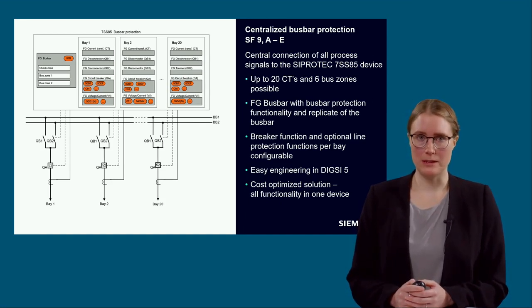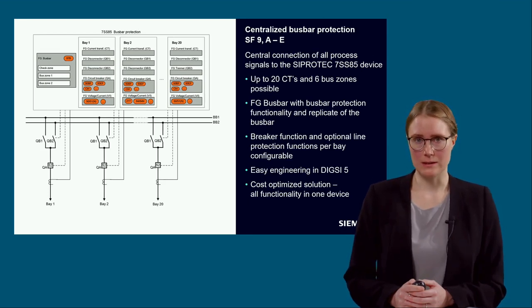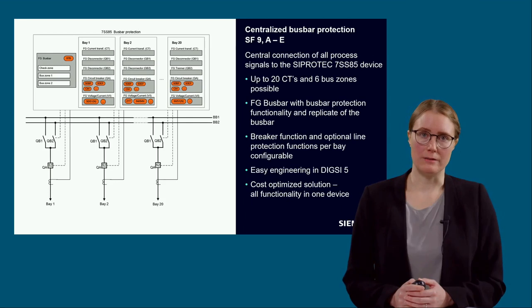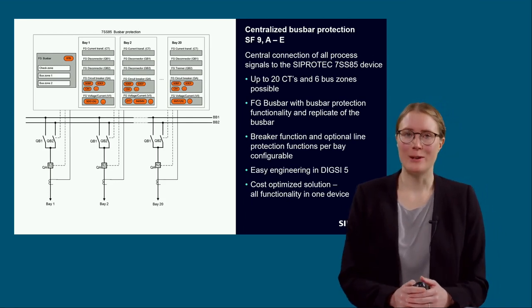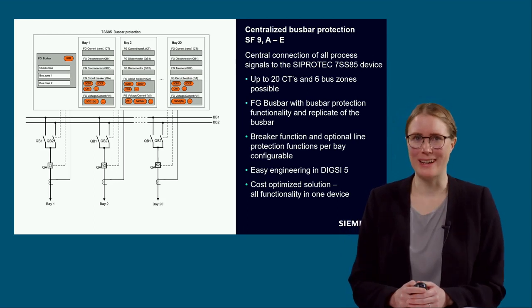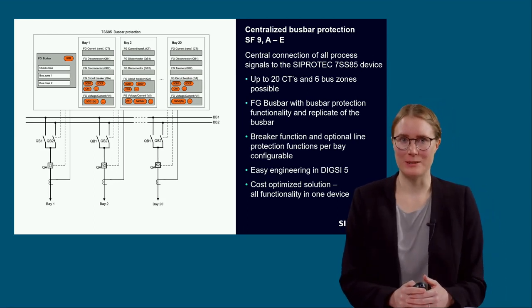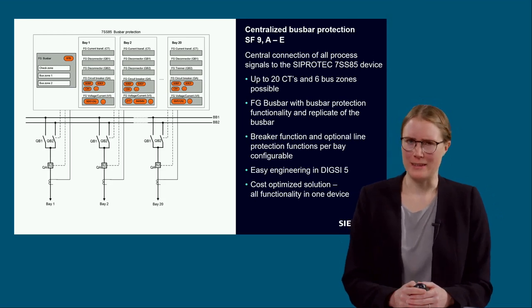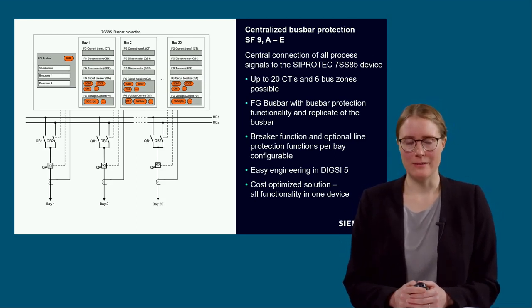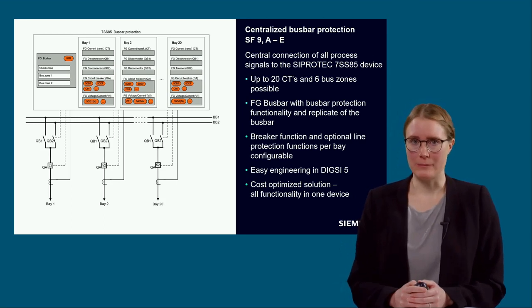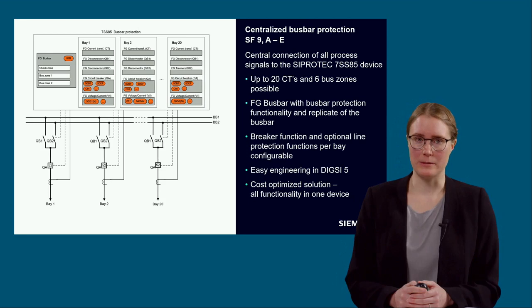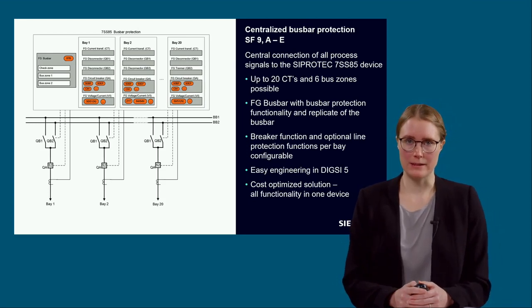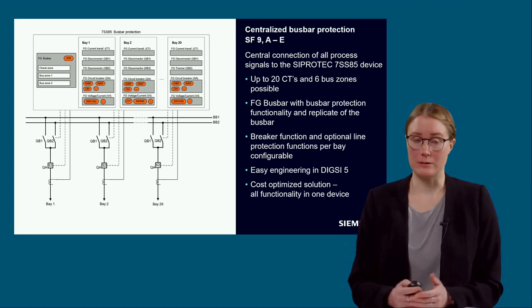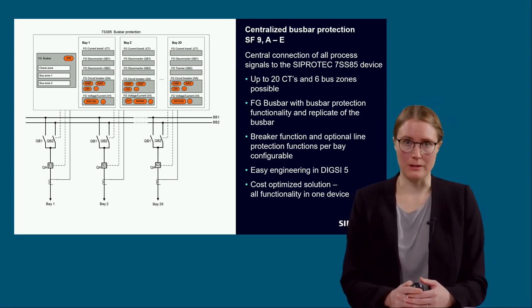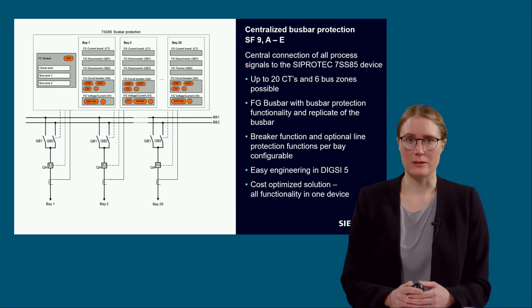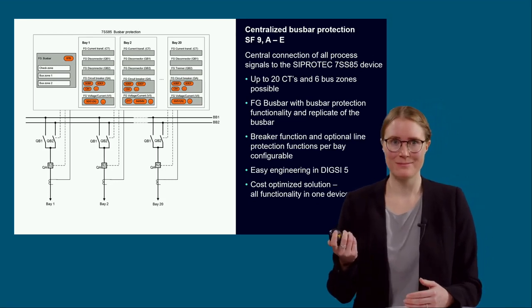For the centralized busbar protection, the so-called significant features 9 and A to E are relevant. Rainer will explain later what the significant features are all about. And when I show you the device selection in the SIPROTEC 5 configurator at the end, you will get a better understanding. With the 7SS85 centralized, up to 20 measuring points and 6 bus zones are possible. The 7SS85 centralized is a cost-optimized solution because you need only 1 device. You can learn more about the centralized solution in our 3rd tutorial next year.